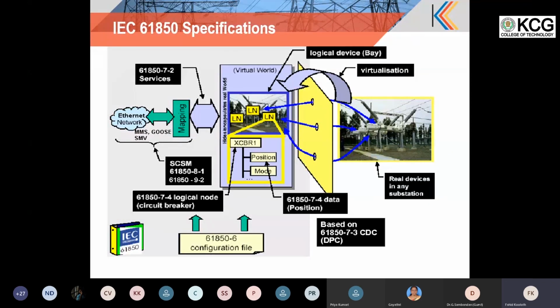What are the data elements needed under this functionality to achieve the functionality? So they have defined all the data needed. Circuit breaker, XCBR, is a logical node associated with the circuit breaker. Position is one of the attributes. It can be a status of the position or a command of the position, and mode, whether it can be a blocked condition, remote command can be issued, or only local command can be issued. So mode is another functionality. All that are defined. So the logical node, its data elements are defined.